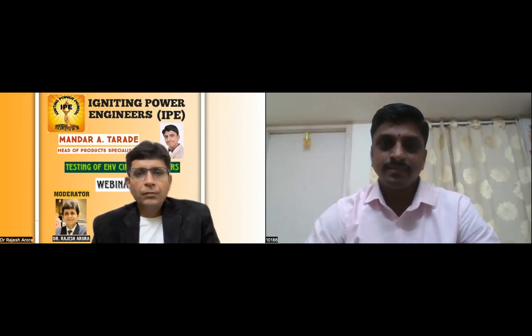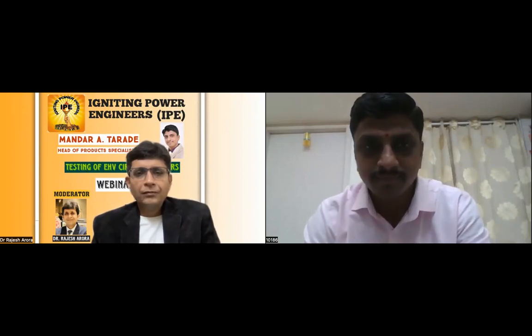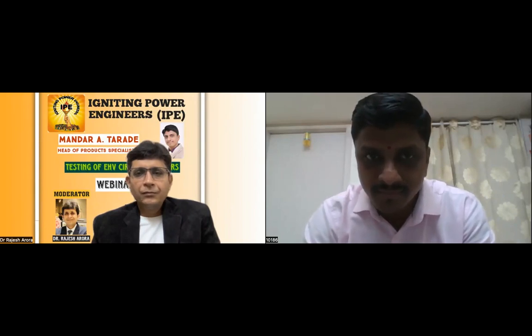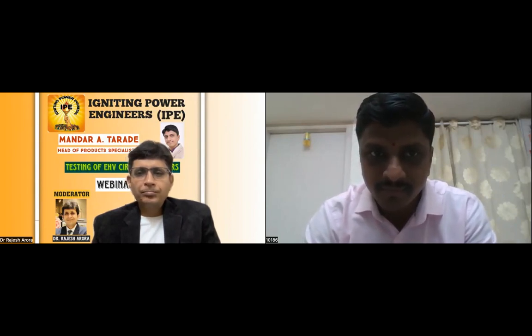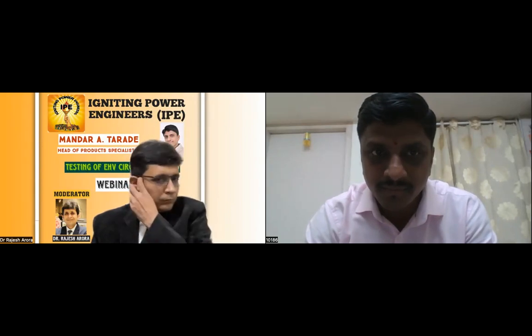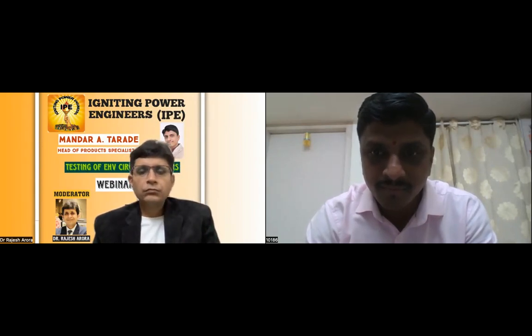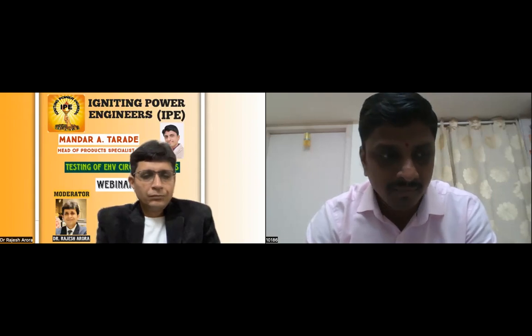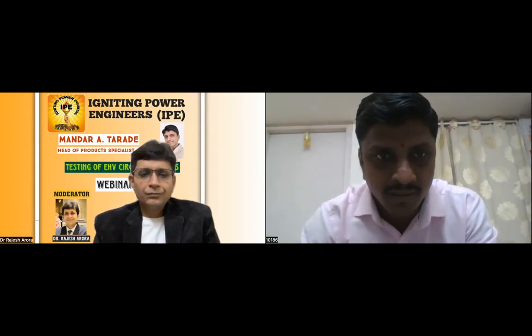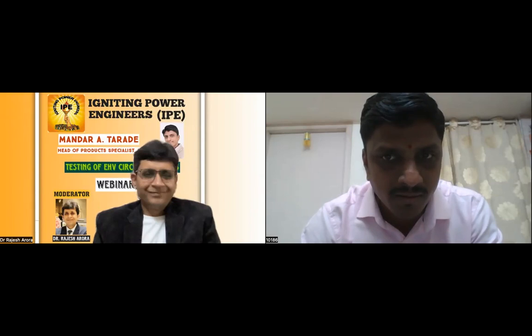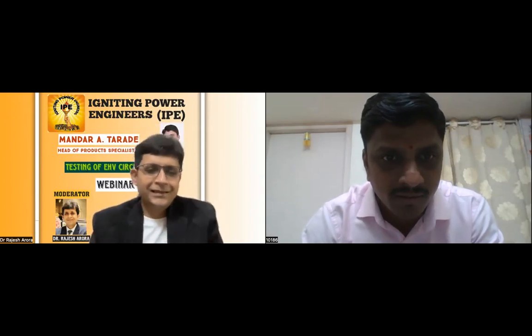Sir, I'm Neeraj Singh. I wanted to know what is the significance of rebound time, and if it is beyond the limits, how it can impact the circuit breaker performance. And another thing I wanted to add to Rajesh Arora's question: for CB timing in GIS, there is a special tool by which we can adjust the timing of the breaker. If it is beyond the permissible limit, we can very well adjust that timing. Yes, that can be done. But for an outdoor breaker, that is not possible, I think. That is not possible, yes.